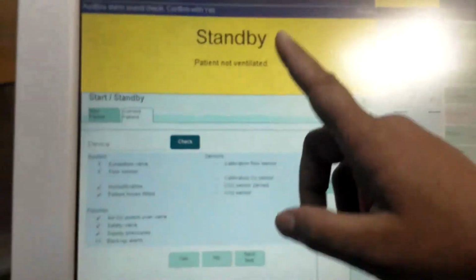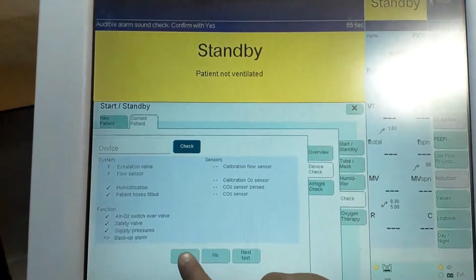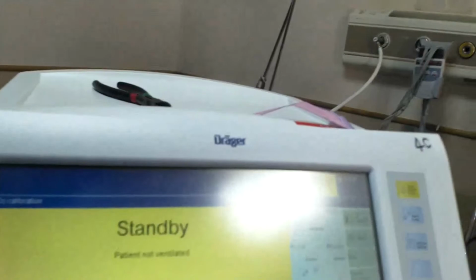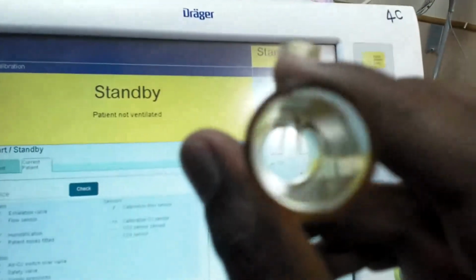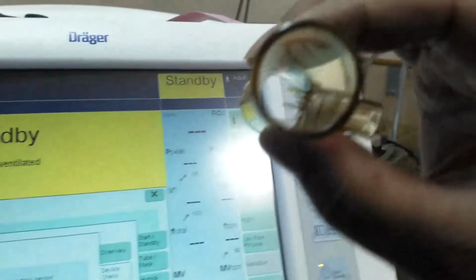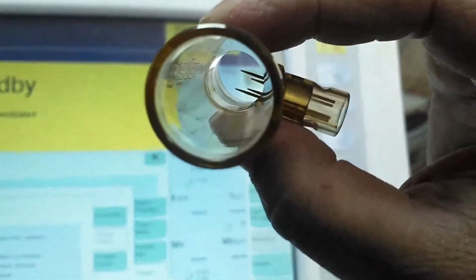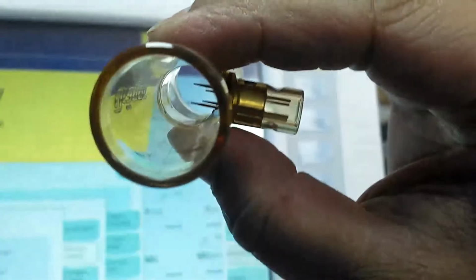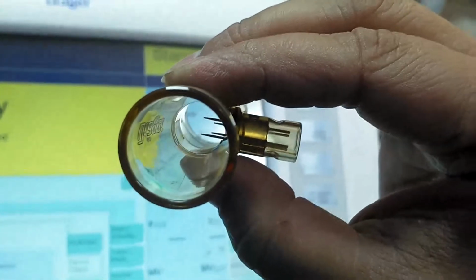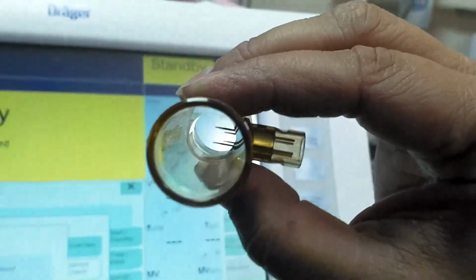Audible alarm sound check. Do you hear the audible sound? Yes. Flow calibration. It is doing flow calibration. Flow calibration failed. Let me check what is wrong with the flow sensor. Okay, the flow sensor is defective. Inside this flow sensor there are two filaments, and if you observe clearly, only one of the filaments is intact and the other filament is disconnected. So we'll take a flow sensor from there.